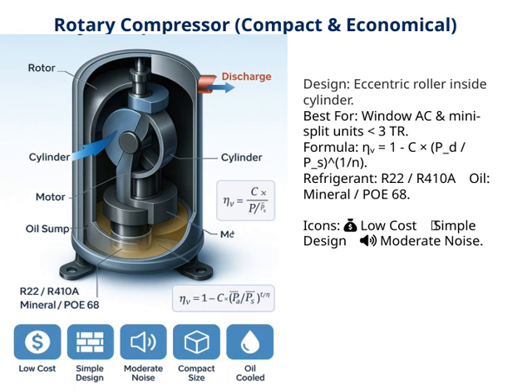When it comes to efficiency, there's a specific formula to understand the volumetric efficiency, or eta_v, of this compressor. It's calculated as 1 minus a constant multiplied by the pressure ratio raised to a power. This helps us gauge how well the compressor performs under different conditions. In terms of refrigerants, the rotary compressor can work with common options like R22 and R410A. As for lubricants, mineral oil or POE 68 are typically used, depending on the specific refrigerant and application.